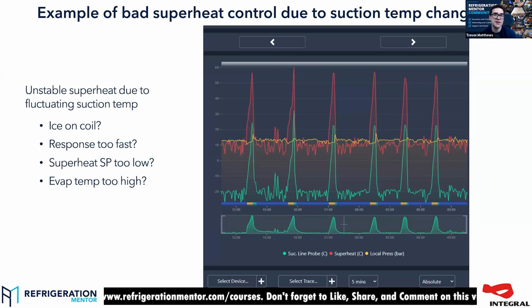And I see more and more CO₂ systems now with lots of different controllers. And even when Chris Prom and I did a podcast, we talked about how you can use temperature first, superheat second. Because we want to try to maintain that product, we want to absorb that heat, we want to pull it out. So when I'm talking to technicians in our CO₂ program, you want to understand how that's set up, because you don't want one case set up by superheat control. The next one right beside it's temperature control. You know what I mean? And you've got to have them set up in the same range, because you want to maintain the product.